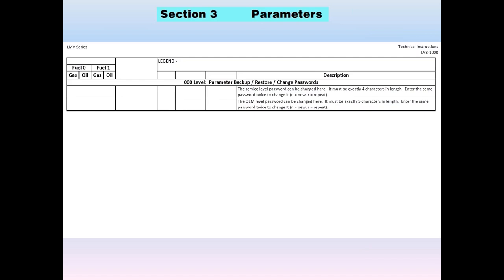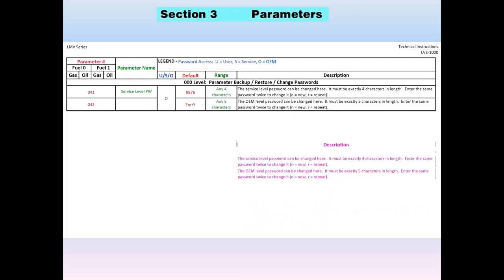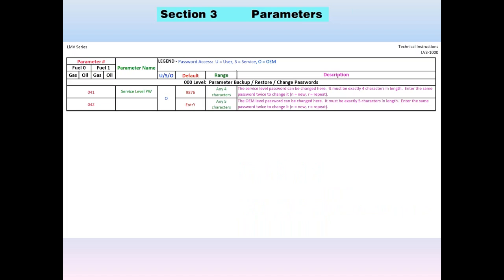The LMV3 starts with an extensive parameter listing chart. It shows the parameter number — for example, 41 and 42 are the passwords — the parameter name, and a column for access level: user, service, or OEM. To change any passwords, you must log in at the OEM level. Default values are shown: service level is 9876, OEM is 'entry'. The range is also shown — the service password is always four characters, OEM is always five. Finally, a description tells you how to enter a new password and what other information applies.